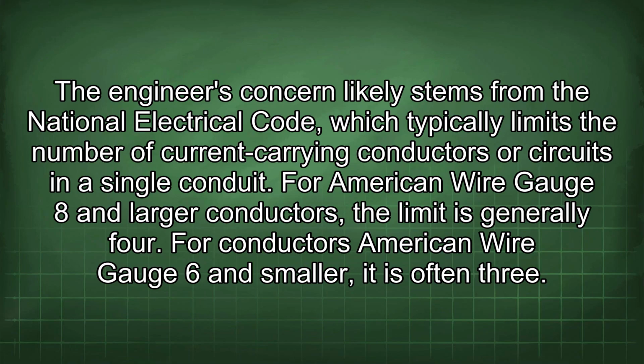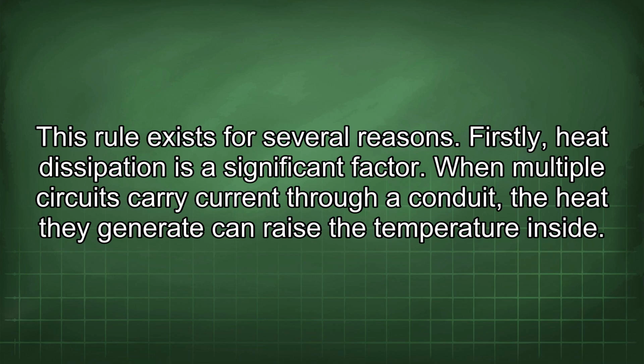The engineer's concern likely stems from the National Electrical Code, which typically limits the number of current-carrying conductors or circuits in a single conduit. For American wire gauge 8 and larger conductors, the limit is generally 4. For conductors American wire gauge 6 and smaller, it is often 3. This rule exists for several reasons.